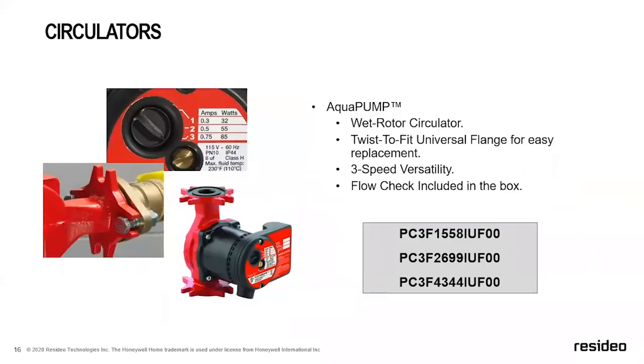And when you look at this next image, we have 3 different selections for speed. So you've got 1, 2, and 3. That goes for our 3 different sizes of pumps. What's shown before you is our 1558, which is the smallest of the 3 we offer, although we also go up to 2699 for the medium size and the 4344 for the largest. With that 3-speed selector, you get a lot of cross-reference. I'll show you on the next slide that this pump has 3 different pump curves on it, and the flow rates will be documented in an install manual. But true 3-speed versatility, twist-to-fit universal flanges, so it's really easy replacement.